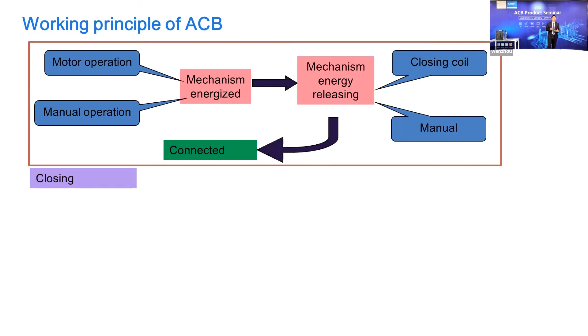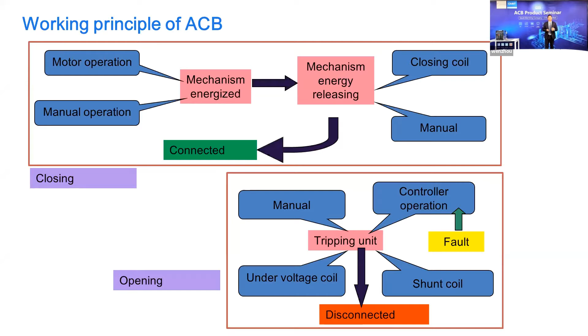And also for the opening, for the disconnecting, we have 1, 2, 3, 4 parts. Firstly, the manual: we touch the off button. Second, the undervoltage coil. The third is the shunt coil. But the fourth one is the most important for the ACB. This means controller operation. Because inside the controller we have the CT detecting the current. If the current is more than the setting, like I set 1,000 amperes, but now the real current is more than 1,000, like 2,000 amperes, the controller will work. It sends the signal to the trip unit, and the trip unit, like the operator, will disconnect the ACB. This is the working principle of the ACB.